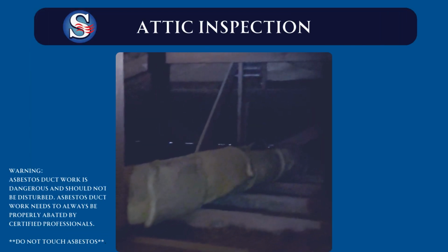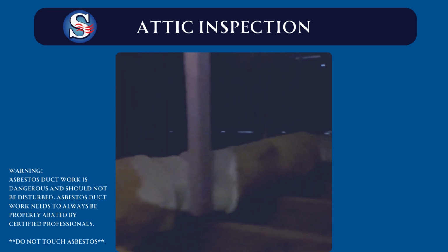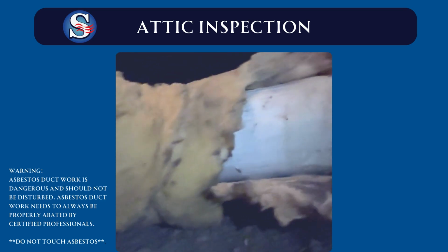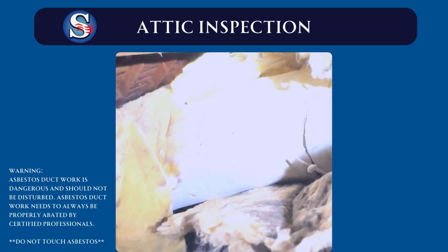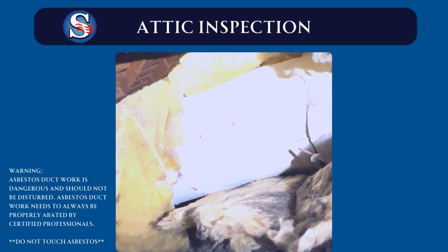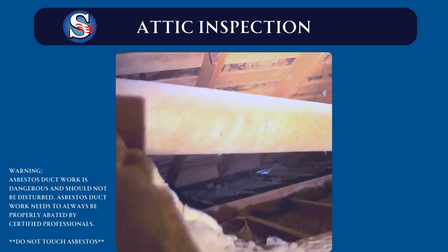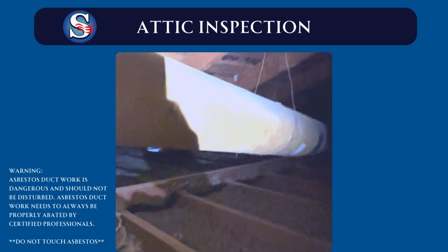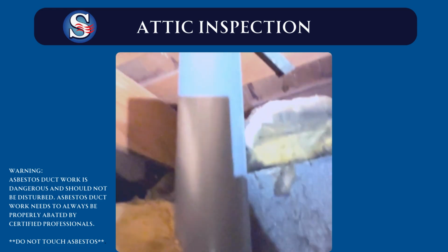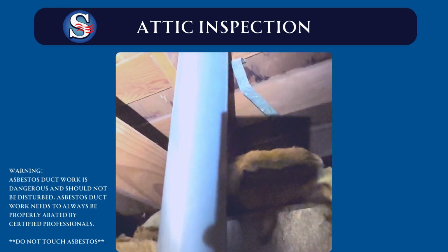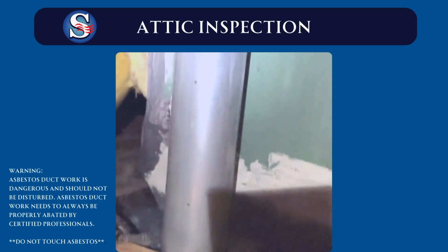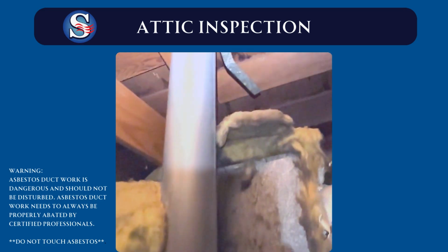So it's important that you inspect the attic, make sure all the ducting's intact and sealed. This is asbestos ducting here. You don't want to disturb that at all. That's a different type of ducting. It's pure fiberglass. And this is your vent pipe. Always want to make sure that this stays connected. It's like an exhaust for your car, but it's for your furnace.